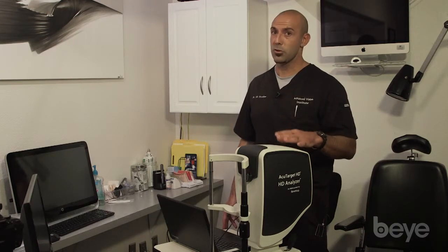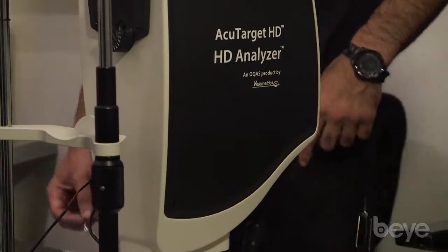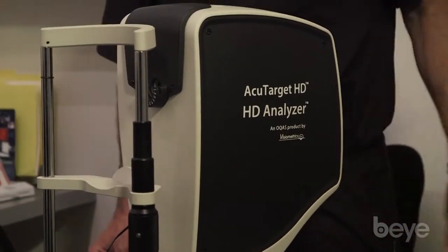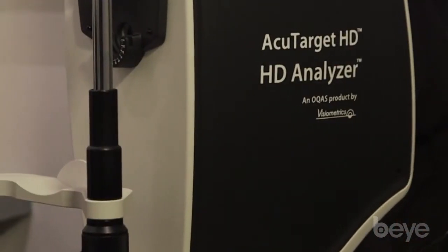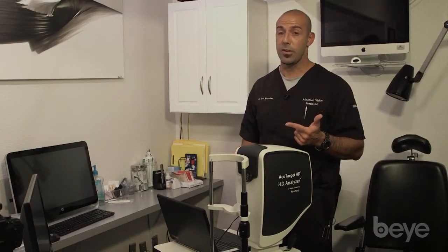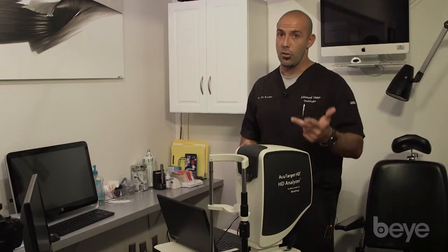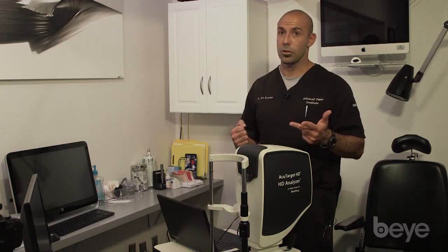So here we have one of the latest and greatest diagnostic instruments for an optometry or ophthalmology practice. The AcuTarget HD is a 4-in-1 diagnostic instrument. It measures forward light scatter in the eye, which measures quality of vision through an OSI scan. Secondly, it measures a tear film analysis to understand how a patient's tear film or their dry eyes is affecting their quality of vision.